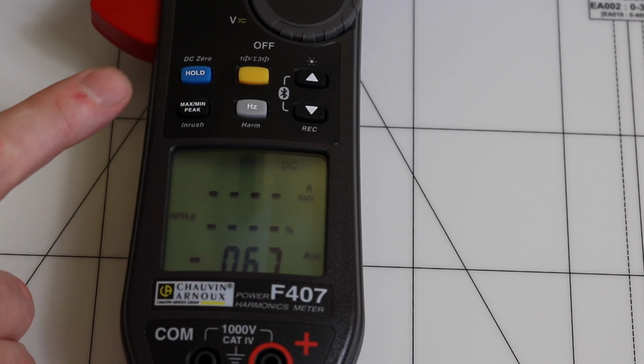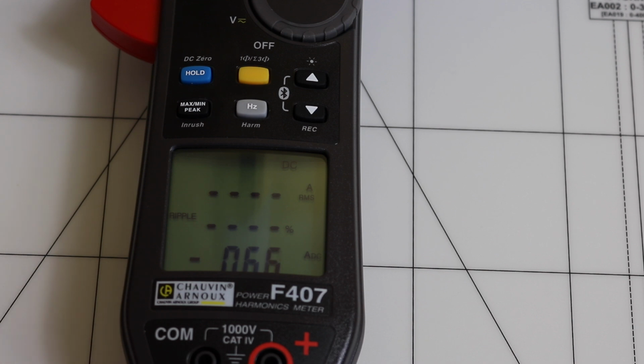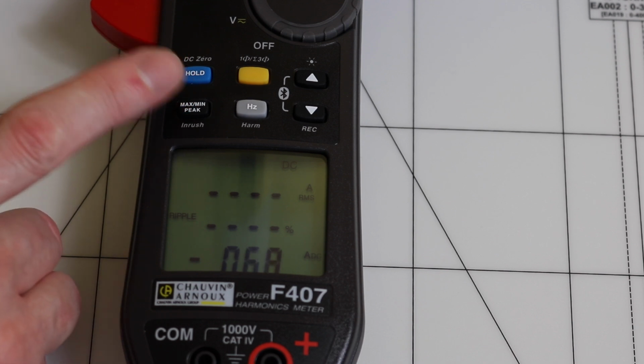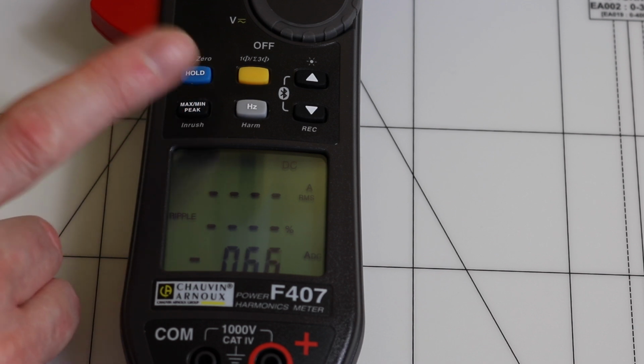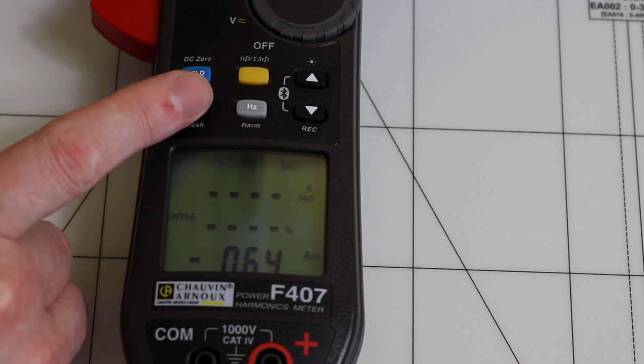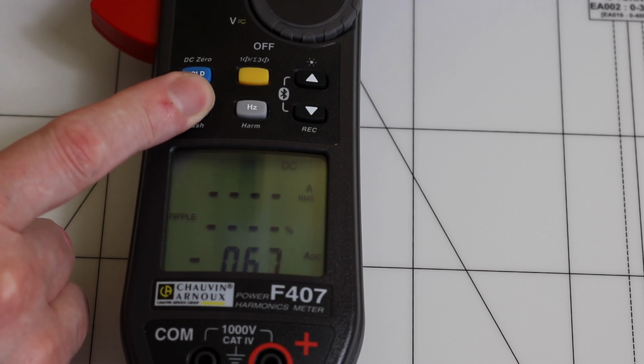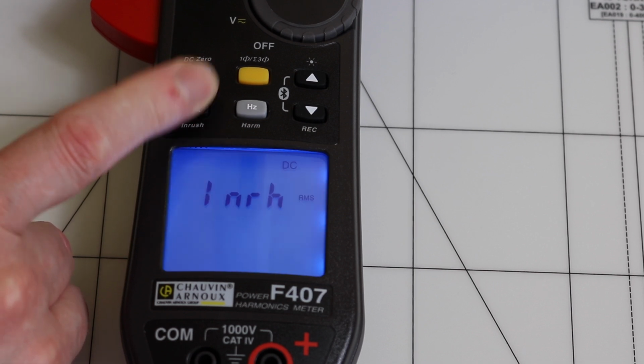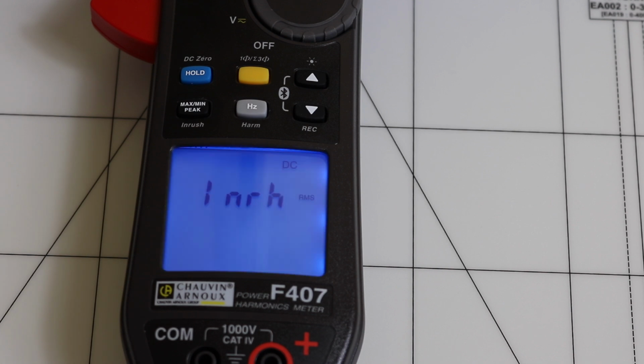When I'd hold down the inrush button, it would just beep at you and there's no dice, it won't switch to inrush. Whereas on this instrument, it will follow exactly the same procedure. I'm going to leave the current switched off, so it should select the minimum trigger level, which we'll see is slightly different on DC. So it seems 15 amps. Now, as far as I know, the AC and DC ranges are 100 amps, so that should be 10 amps as well, but for some reason it's 15 amps. We will just go to run our program.